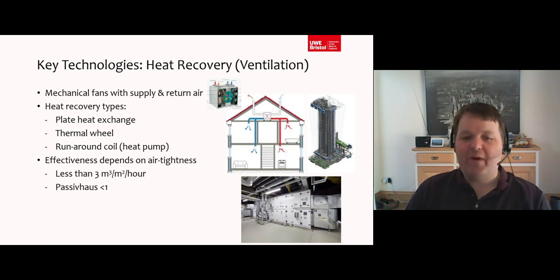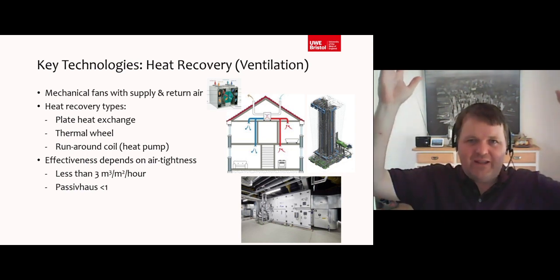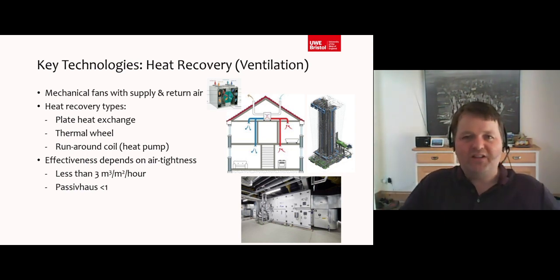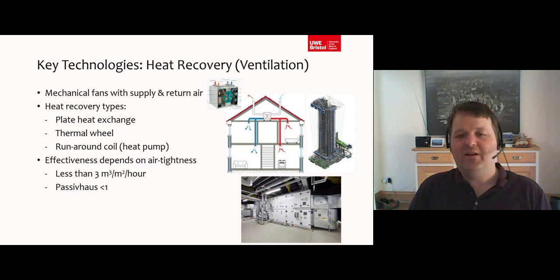The effectiveness really depends on the air tightness of the structure. So we had a good example here a few years ago. We did an air pressure testing of 3 houses in Bristol that had the MVHR technology. One was a DIY. Someone bought the MVHR, brought it back to his house, stuck it in the attic, put it on the tubes, and then went around his house sealing it up himself with silicone and expanding foam. And we did an air pressure test of that structure, and we found it to have a value of 7. Now, you have to have 3 or lower to be efficient, or feasible for MVHR. His was 7, so it wasn't actually efficient.